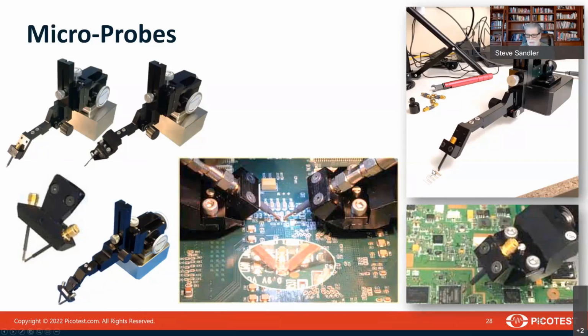And the calibration is a specific point on the pad. So you'll see that there are instructions about where the two pins have to contact the pad and how to place Mylar tape over the calibration structure so that you can make dents in the tape to make sure that you don't over-compensate the pressure. So we can just dent the tape, and then we can remove the tape and repeat the placement of the probe using a finite number of fixed turns of the positioner.